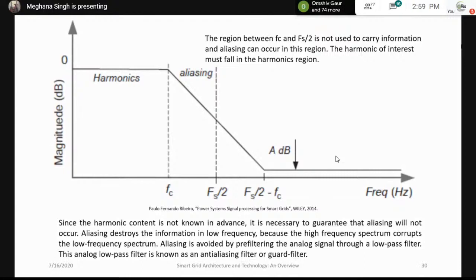If aliasing occurs, you have to rule it out, so the harmonic of interest must fall in the harmonics region itself, not the aliasing region. If you look at the diagram, there is a harmonics region and an aliasing region - I have to focus on the harmonics region. If the harmonic of interest falls between fc and Fs/2, there is a problem, and it will crop up into multiple issues.